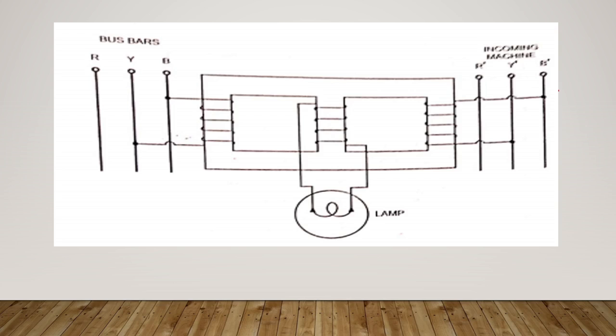When two alternators are in exact synchronism, the two alternators will have equal induced EMFs which are in exact phase opposition. No circulating current will flow around the local circuit. When the EMFs induced in the two alternators are equal in magnitude but are not in exact phase opposition, the resultant EMF will act around the local circuit and cause the flow of a current called synchronizing current.